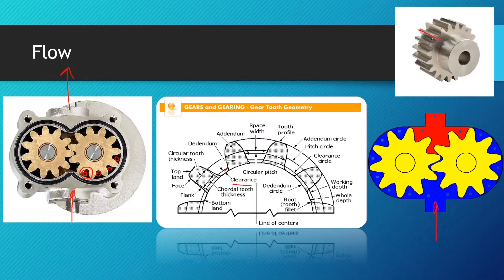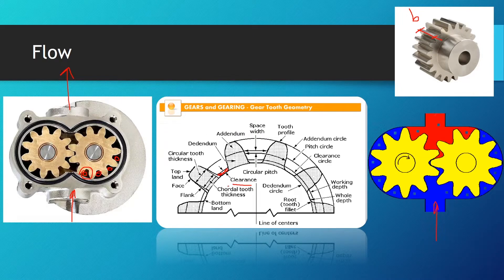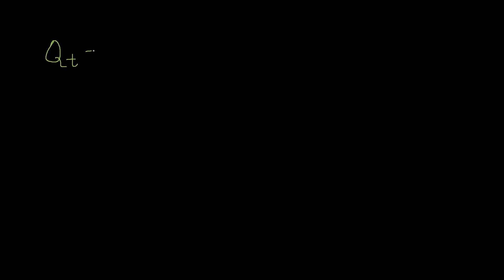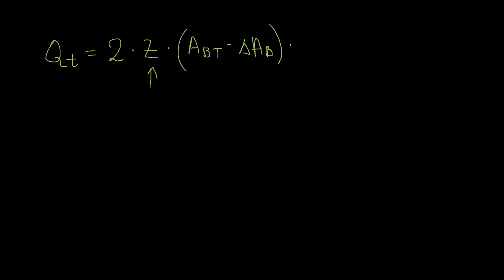So the effective area is the area between teeth minus the clearance area, times the width of the gear b. The equation for theoretical flow is: qt equals 2 times z, where z is the number of teeth and we use 2 because we have two gears in our pump. If there were n gears you would put n times z. Then we multiply by the area between teeth minus the clearance area between teeth, times b.